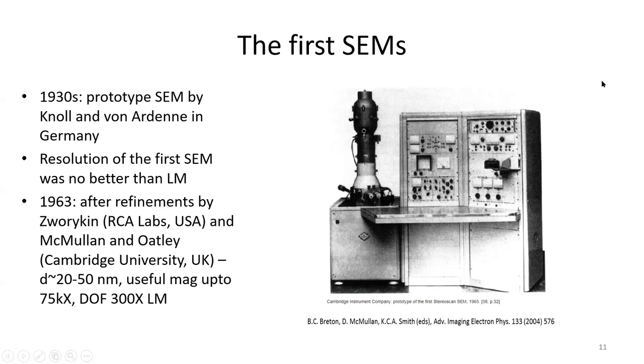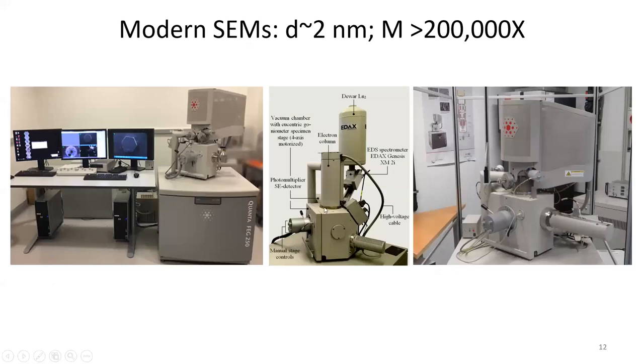You could see that the electronics are quite big, and this was quite big equipment at that time. The modern SEMs look like this, and the resolution is 2 nanometers and magnification is more than 200,000 times. So these are different components of the SEM. The SEM is a much smaller equipment than a TEM. The TEM column is quite tall, quite big, long. In comparison, the SEM column is a little short. This is the electron column, and you have a chamber here. Here is the source of electrons, this cable you see here. This is the electron gun, the source, and this is the column through which the electrons travel.